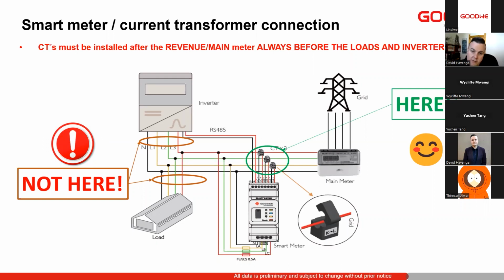I know sometimes we need to remove the CTs off the top of the smart meter, because the smart meter might not fit into the customer's distribution box. So we need to install an external box next to that. Then we'll install the smart meter, remove the CTs, and place them back on the device. It's very important to check that we put the right CTs on in the right place, and that the voltage input to the meter is the correct voltage and the correct input. And then lastly, the direction of the CT should always be K to L, so from house to grid. So K is house, L is the grid. It's very important that we do this correctly.